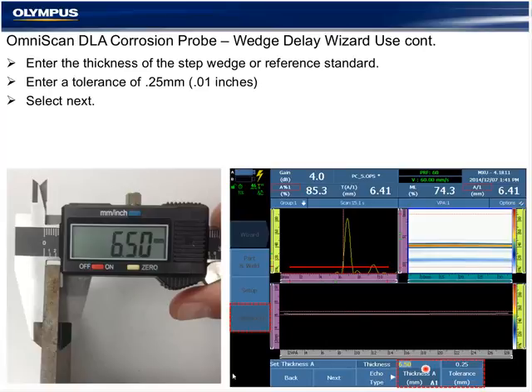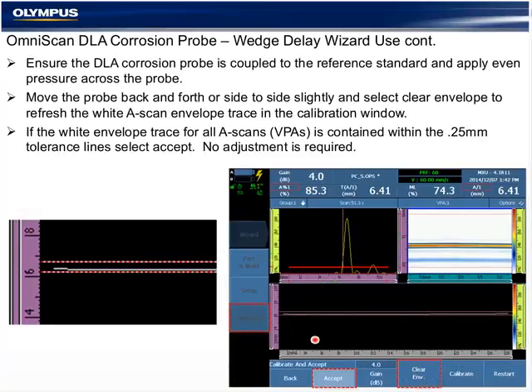So entering the wedge delay, select the good number, enter in the tolerance for the probe, and under almost all situations, if this is carbon steel and the velocity of your component is within about 50 meters per second of the default value for carbon steel in the OmniScan database, your probe wedge delay or thickness reading accuracy is going to be within tolerance all the way across the probe. In this case, it is preferable and highly recommended that you not select calibrate to readjust each A-scan's wedge delay, but simply select accept.